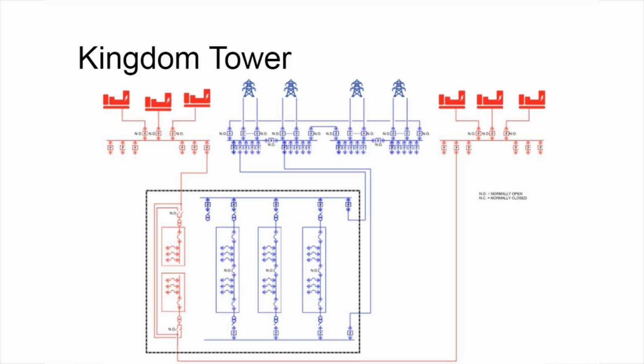So we've set up two paralleling gear emergency power systems that then feed up through the building to unit substations, which are then interlocked together with manual ties so that we can always switch over to the other system if we need to in a critical situation. It was very, very important with a building this tall that we maintain power at all times to provide life safety. And so this was the configuration that we elected to use to help support that building.